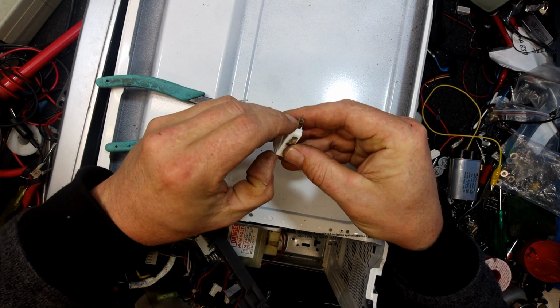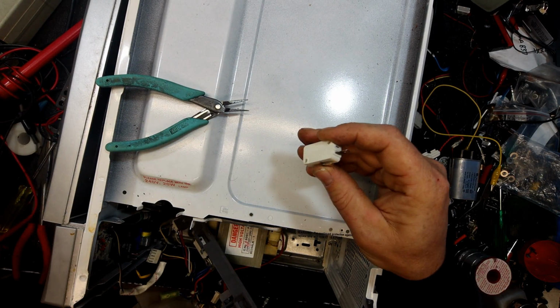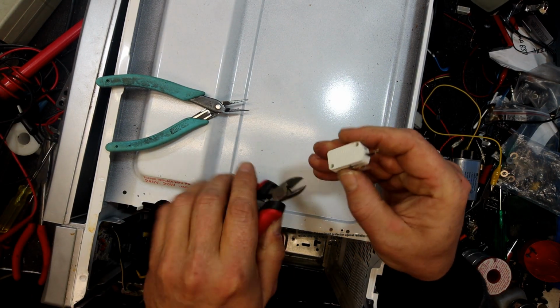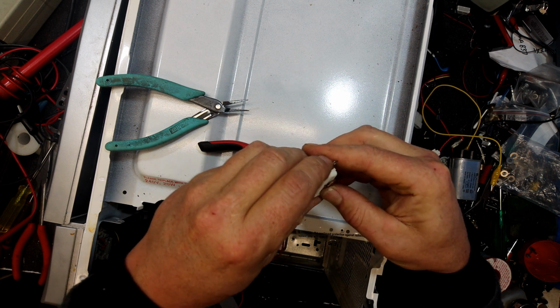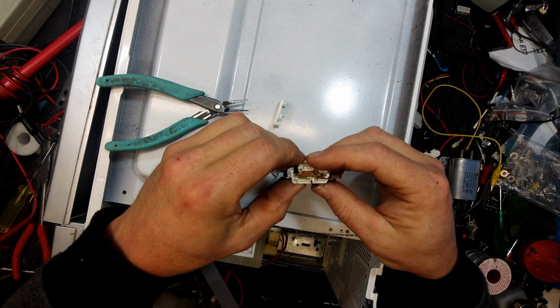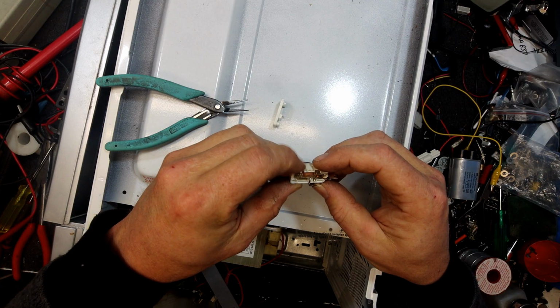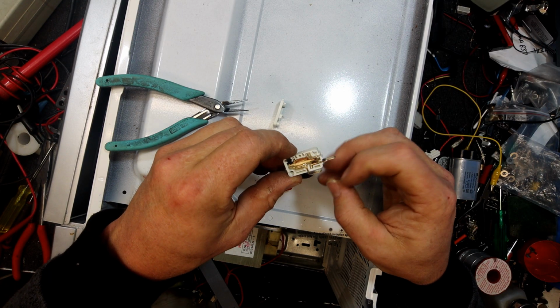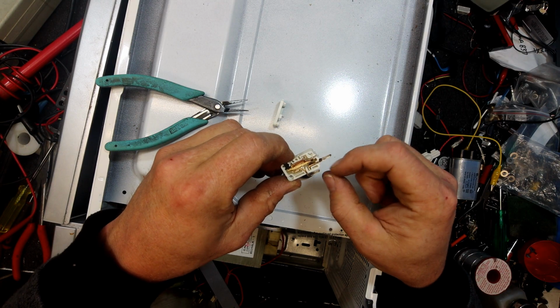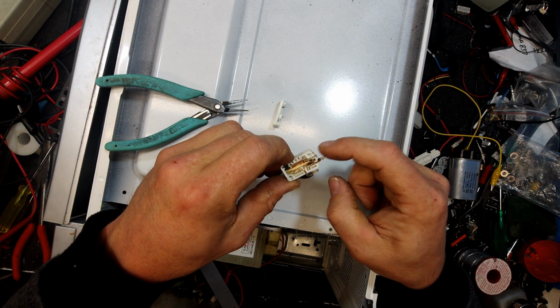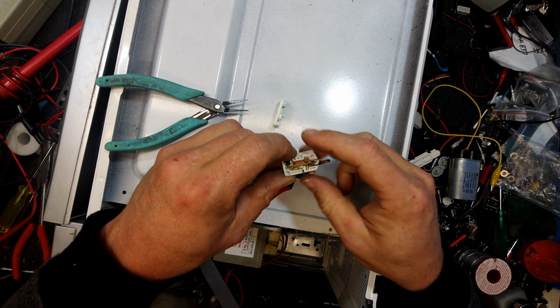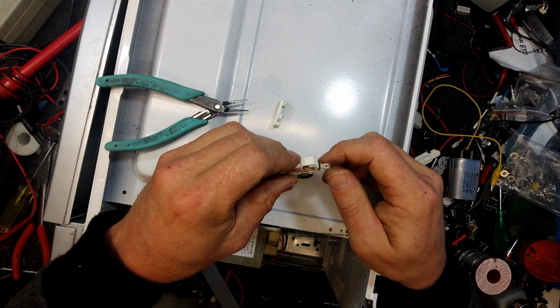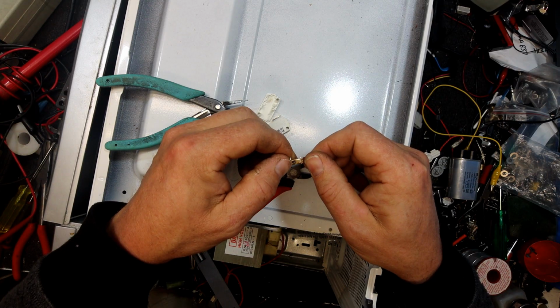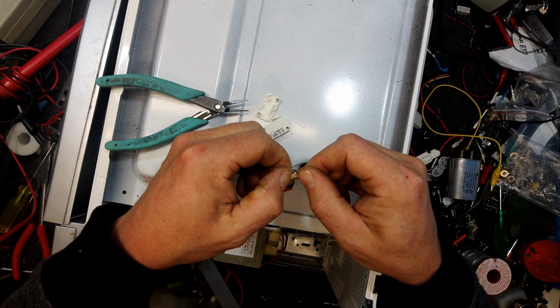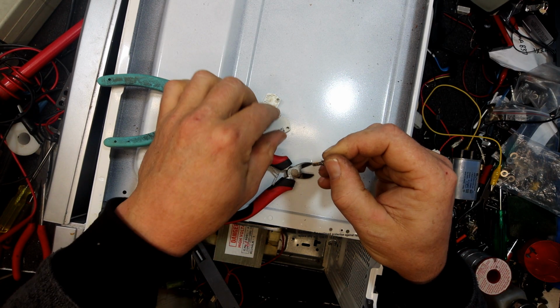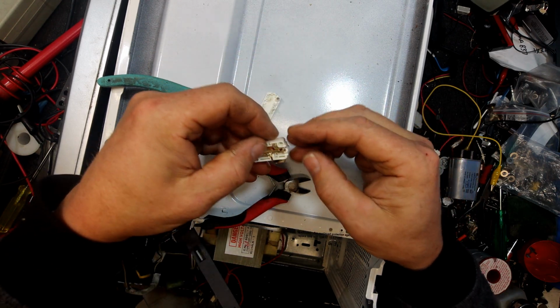What we used to do with these a lot of the time, at least to inspect them, is you can actually pop these switches open. Some of the 3 terminal ones, the single pole double throw, some are normally open, some are normally closed. So you might have a terminal here, 2 terminals, 1 terminal here, 1 terminal there. And this one's not looking the best - you can usually pull these out and have a look. See, she's all pitted and blackened. Not terrible - if they get really bad, you just replace the switch.